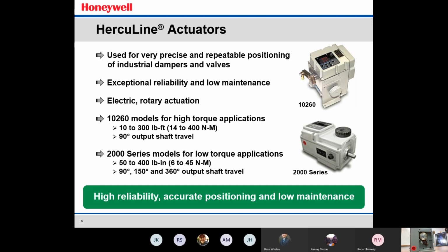rotation on that shaft. On the 2000 series, this actuator came about with the obsolescence of the old Actuator motors. These would be the M740s, the M940s, and the M640s. The new Herculine actuator carries the same footprint as the old Actuator motors and the same mounting as well. The enhancements to the Herculine actuator over the old Actuator motor, the Herculine has also an optional display for configuration, troubleshooting, and calibration.